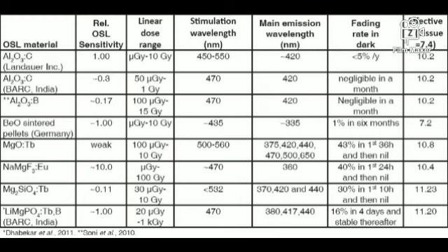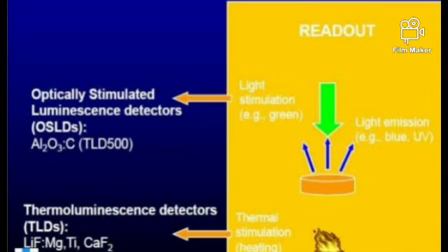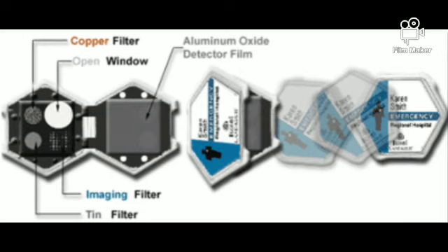To summarize the key difference between OSLD and TLD: OSLD stands for Optically Stimulated Luminescence Dosimeter, while TLD stands for Thermoluminescence Dosimeter. For chip material, OSLD uses Al2O3 with activated carbon, whereas TLD uses CaSO4 with Dy, or LiF. OSLD is generally considered better compared to CaSO4-based TLD chips.